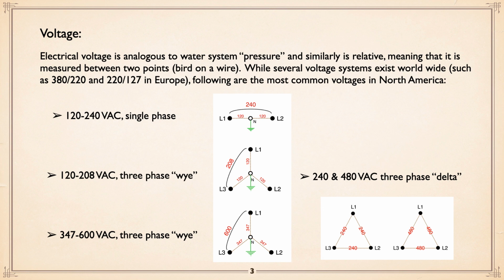There are several different voltages, quite a few actually worldwide, such as 380/220 or 220/127 in Europe, but following are the most common voltages in North America, with 120/240 single-phase AC being used in so many houses. Classically, the contractor will bring in 4 wires, a black, a red, a white, and a green. Now, the green is simply a safety for ground. But the black and the red, line 1 and line 2, if you measure between them, you have 240-volt single phase, which is used for powering stoves, air conditioners, dryers. If you're between either of those lines and the neutral, you get 120-volt, which of course is receptacles throughout the house.